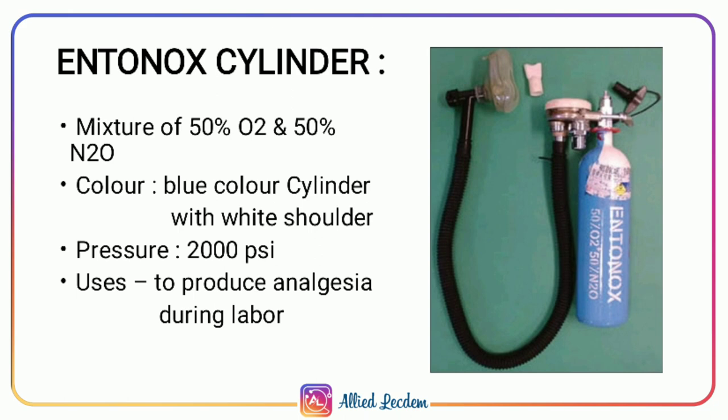Entonox is a mixture of 50% oxygen and 50% nitrous oxide. The cylinder is color coded as blue body (from nitrous oxide) with white shoulders (from oxygen), giving it a blue body with white shoulder appearance. The pressure is 2000 psi. The major use of Entonox is to produce analgesia during labor.